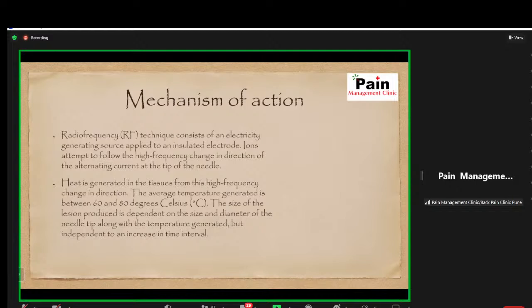Whatever temperature we are looking at is not the actual tip temperature, but the tissue temperature. So the radio frequency probe has a thermocouple. That's why the technology is very costly, because the thermocouple technology, that innovation itself, is a costly thing. The thermocouple in the probe takes the exact temperature at the tissue level. Heat is generated in the tissue from this high frequency change in direction, which causes friction in the ions. The average temperature generated is between 60 to 80 degrees Celsius.